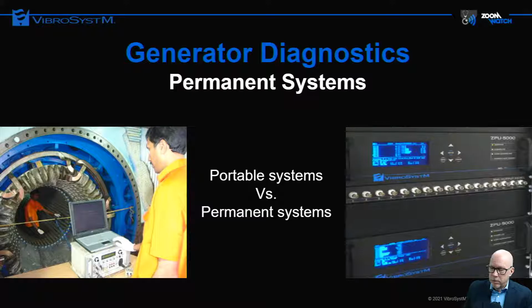So then, from portable systems, the introduction of permanent systems happened. The evolution of monitoring systems was not only spurred on by a need to better protect the assets. As I mentioned before, most of this equipment was set up to be protection equipment. There was a protection scheme, alarms would be tripped and people would get involved. It's not only the need to better protect the asset by adding more reliable and efficient measuring chains along with more advanced acquisition devices and then on to the existing PLC systems, but it was also spurred on by a need to better understand what the monitoring systems were providing as data.